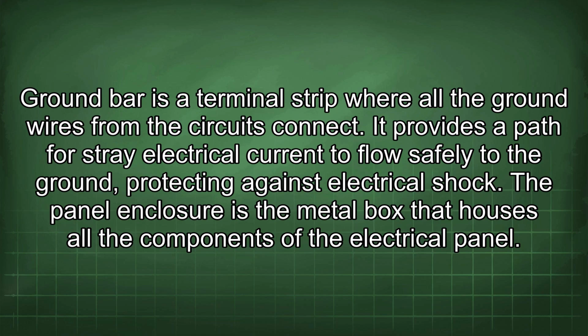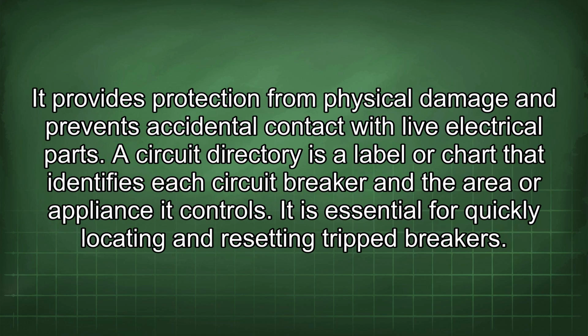The ground bar is a terminal strip where all the ground wires from the circuits connect. It provides a path for stray electrical current to flow safely to the ground, protecting against electrical shock. The panel enclosure is the metal box that houses all the components of the electrical panel. It provides protection from physical damage and prevents accidental contact with live electrical parts.